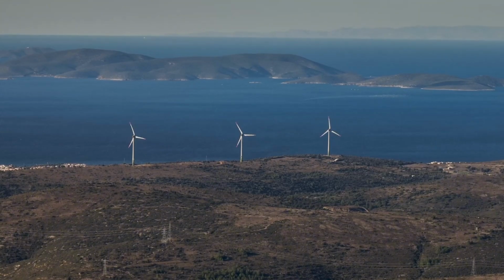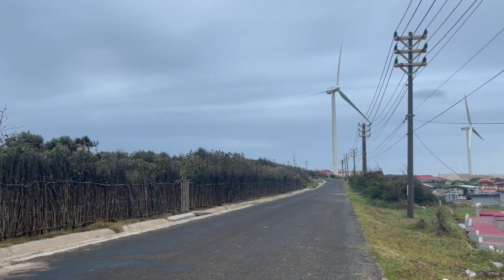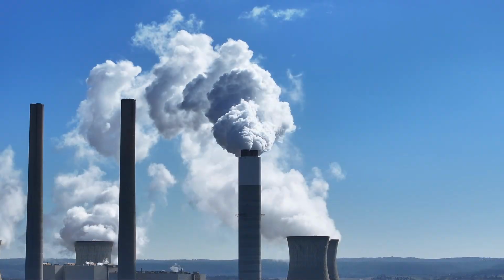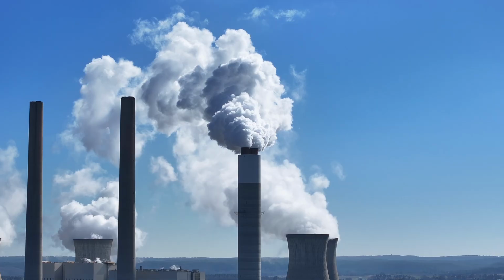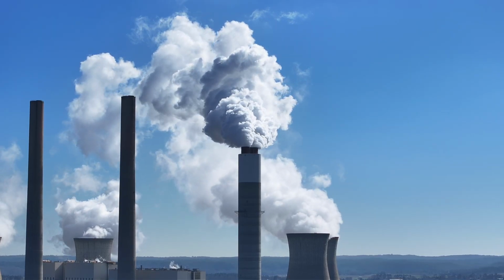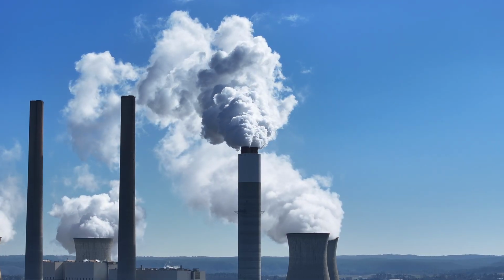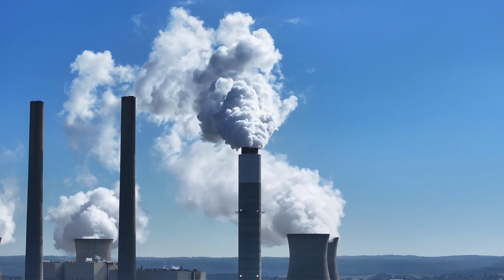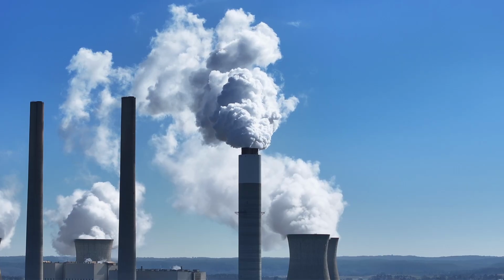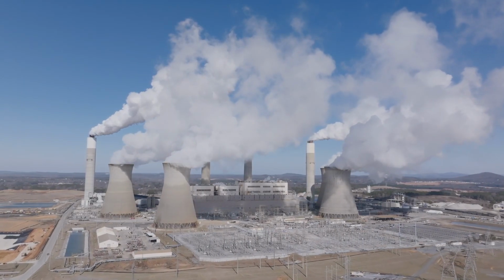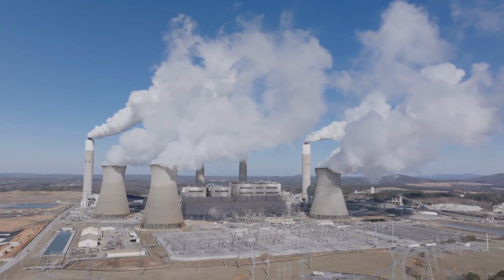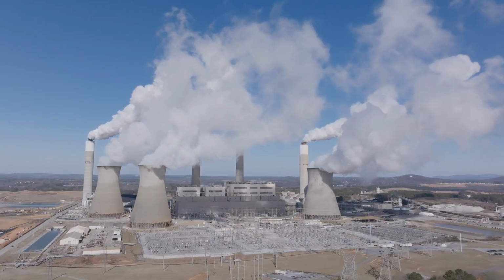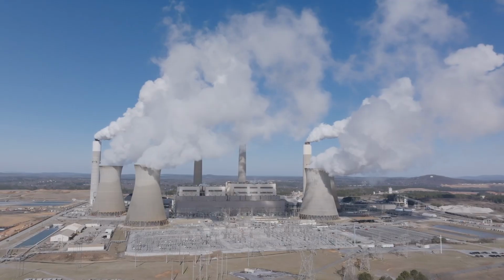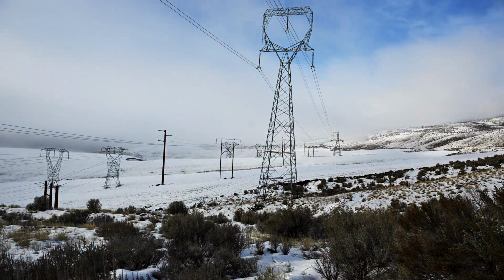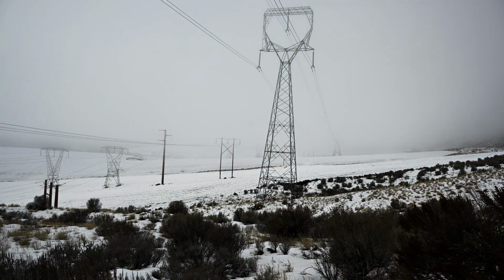If a large power transformer fails today in a high-load corridor, the utility responsible for replacing it faces a procurement timeline of approximately 128 weeks for a standard unit, assuming one can be ordered immediately and a production slot is available. That is 2.5 years during which the substation that transformer served operates in a degraded configuration with reduced redundancy and thinner margins. During those 2.5 years, the demand in that corridor is not declining. The data centers being built nearby are not slowing their connection timelines to accommodate the replacement schedule. The summer heat domes that push regional grids toward their limits do not pause for transformer procurement.